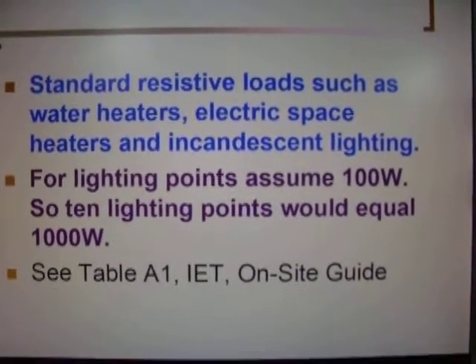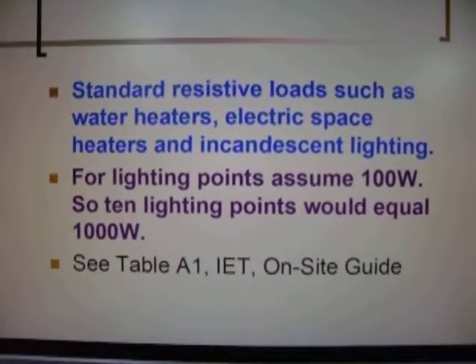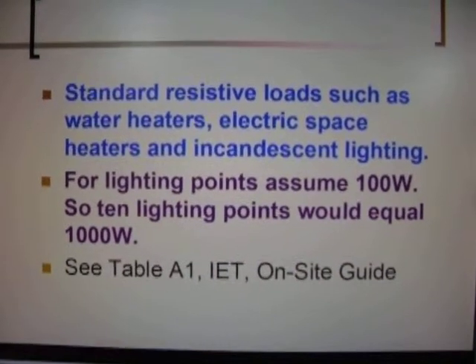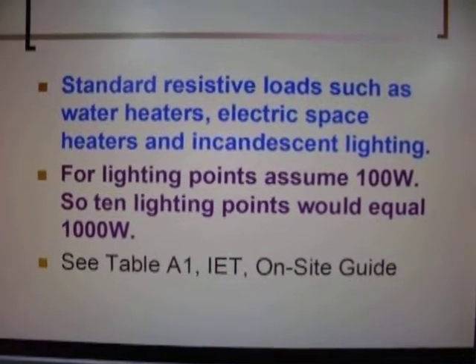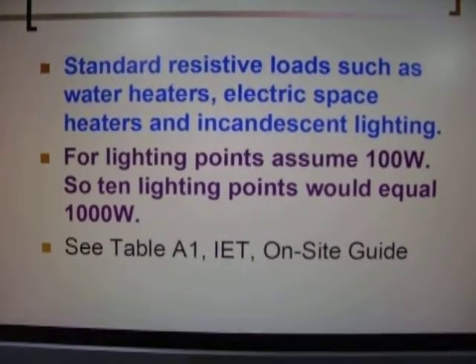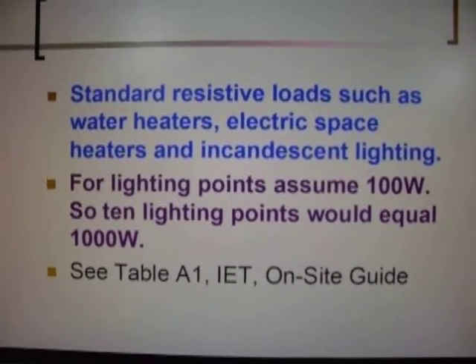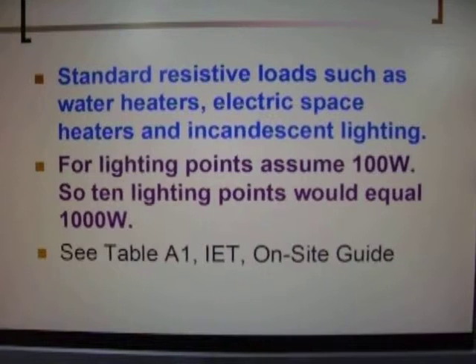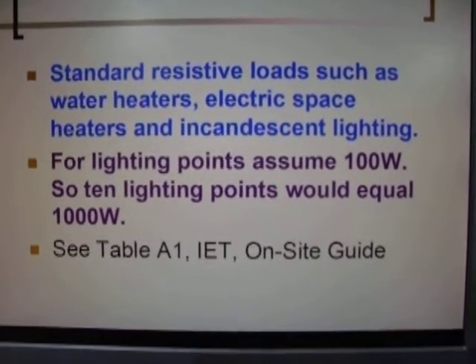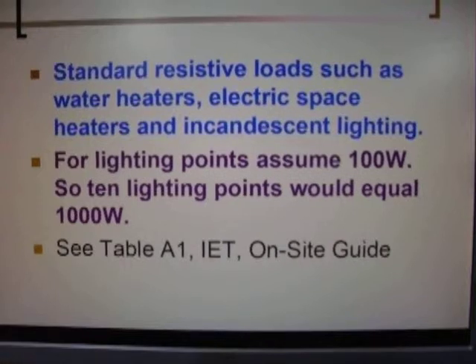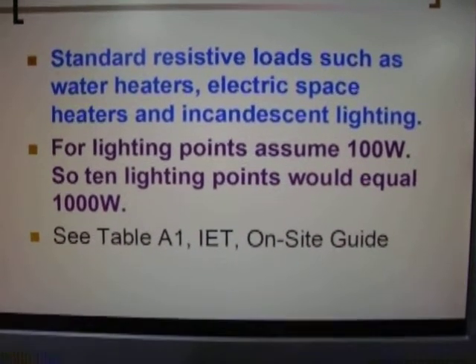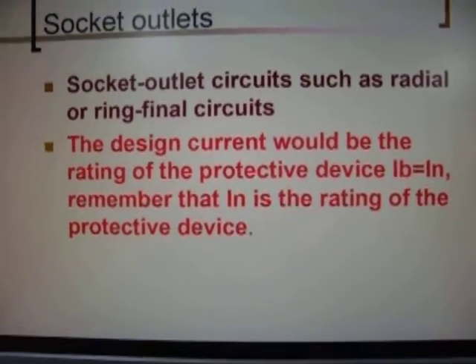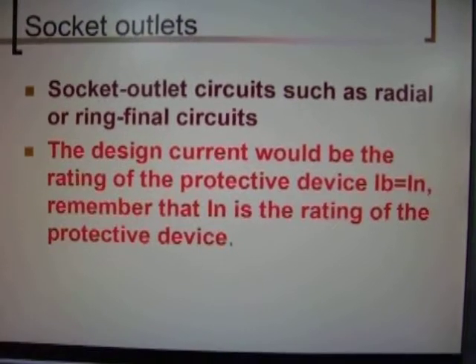For a lighting point, assume 100 watts. For effective lighting we always assume 100 watts. Now I know that we're dealing these days with LED lighting which can operate at 5 watts and give out a tremendous amount of lumens, but we still retain 100 watts for installation purposes. But again, refer to any diagrams or graphical illustration that might be needed or which has been given to specify. Always comply with what has been requested.